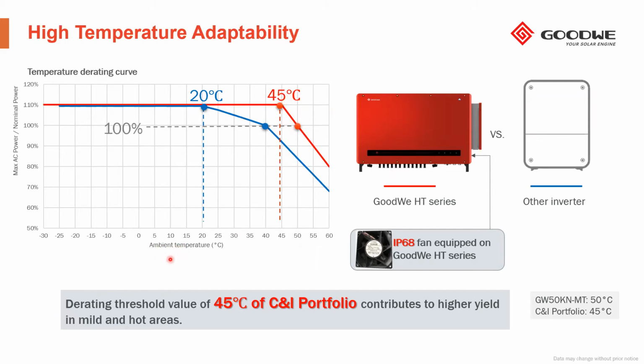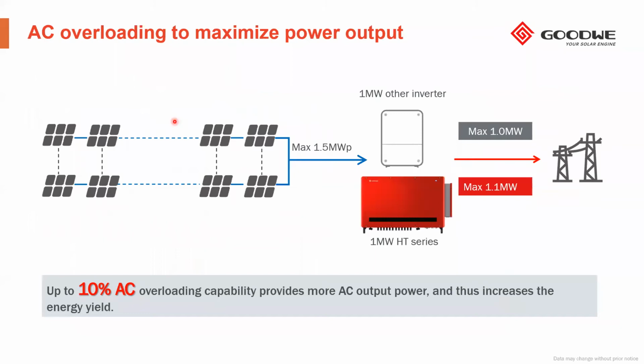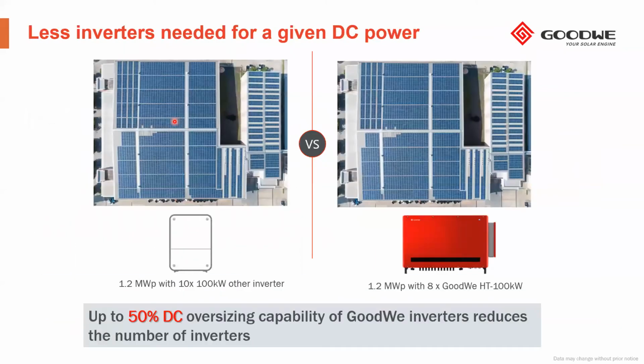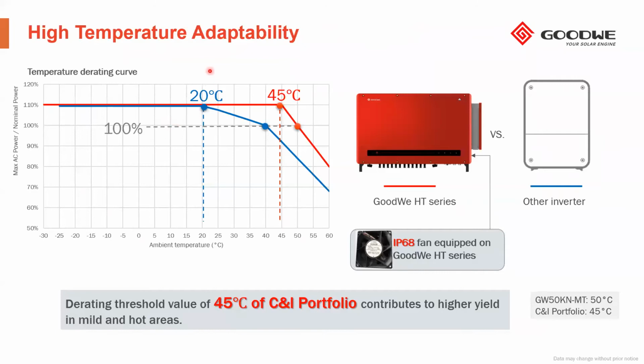And this is very significant because in our competitors, you can see that really relevant competitors, the threshold is 20 Celsius degrees. And let me highlight here that we are not talking about 100% of the output. This is the output power of the inverter. You see here the 110%. So that means, let me come back to the previous slide, we are considering this scenario that also is related with this scenario. So the DC oversizing, the AC overloading, and the derating is linked somehow.